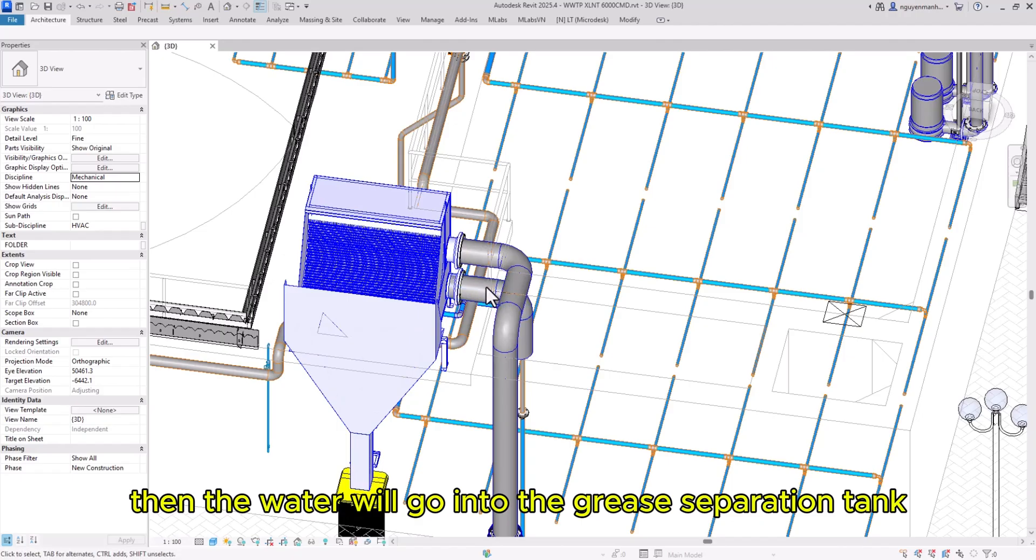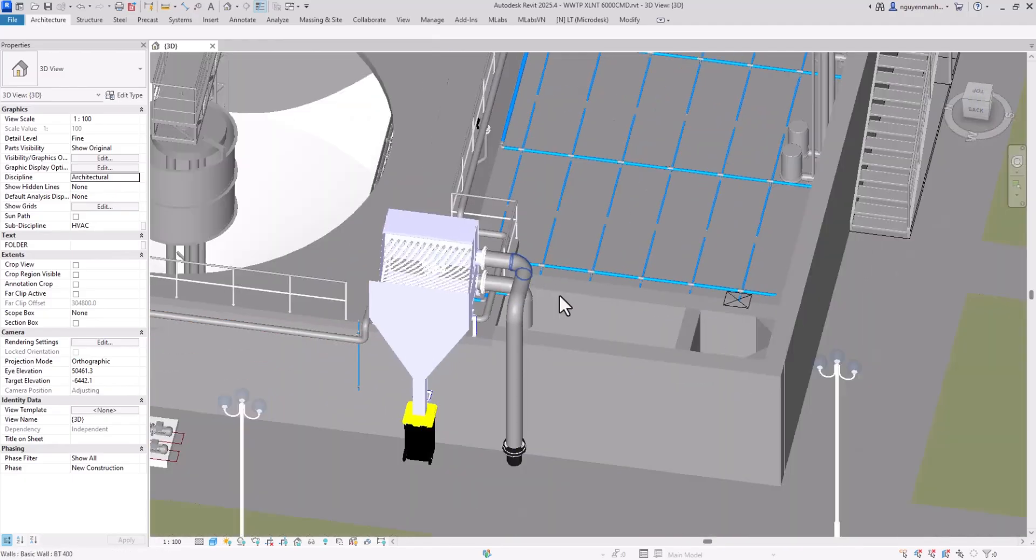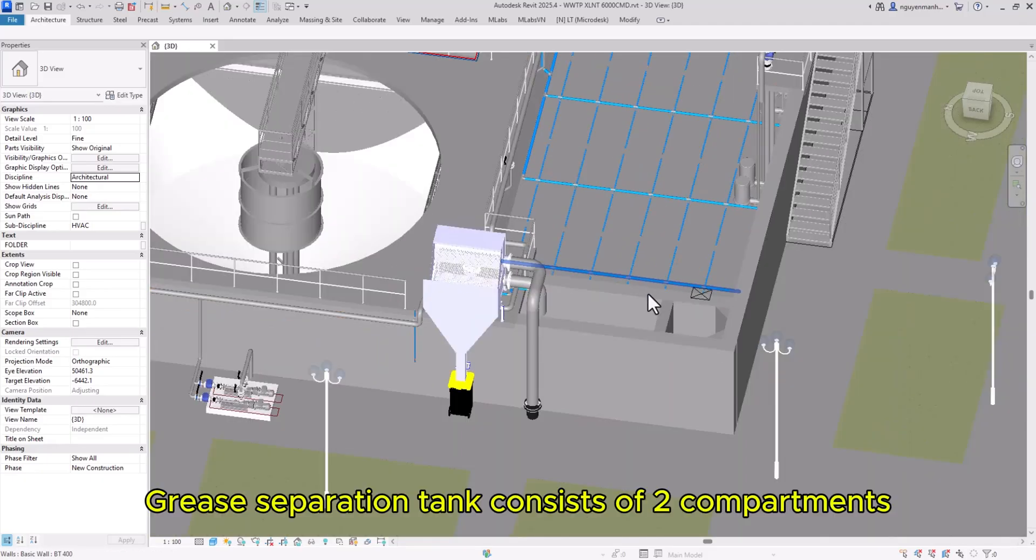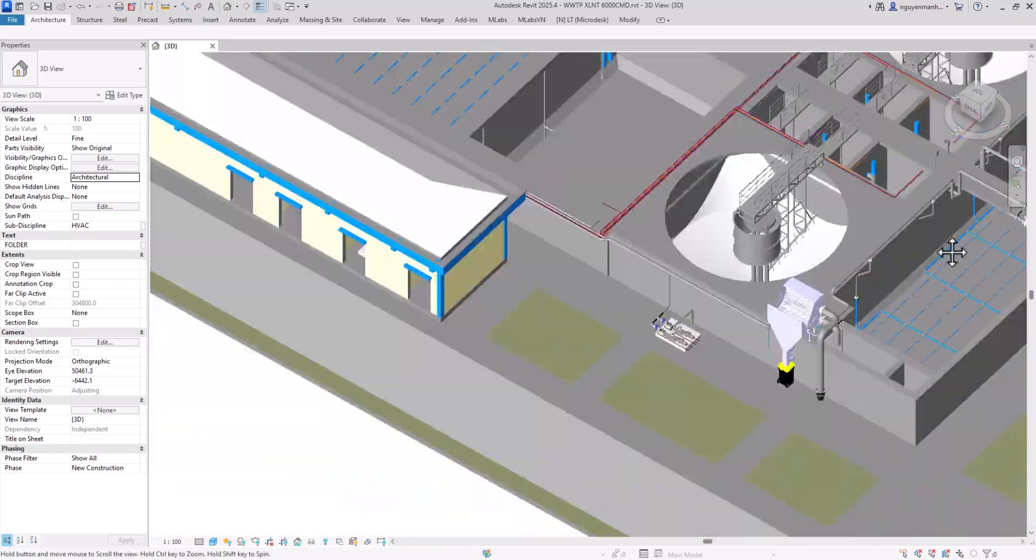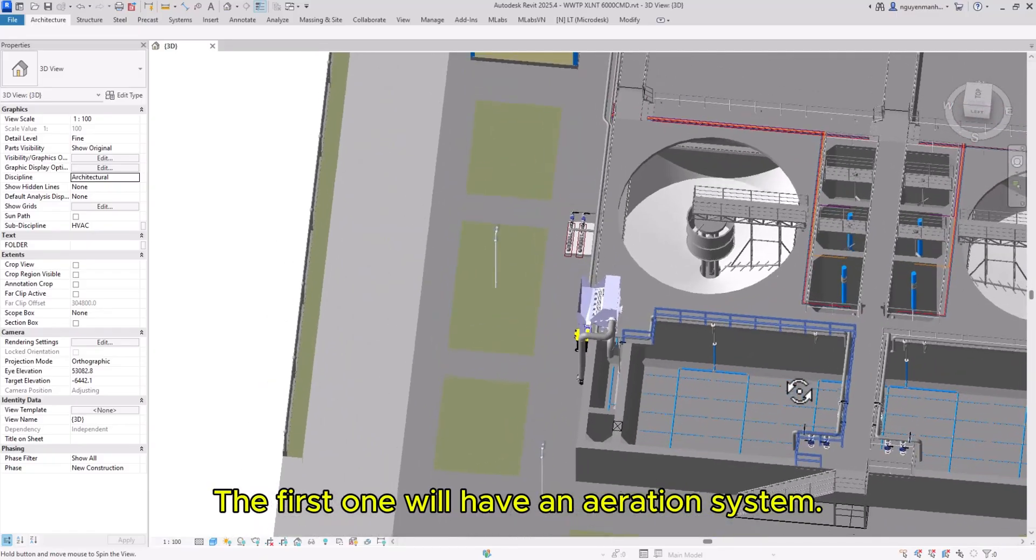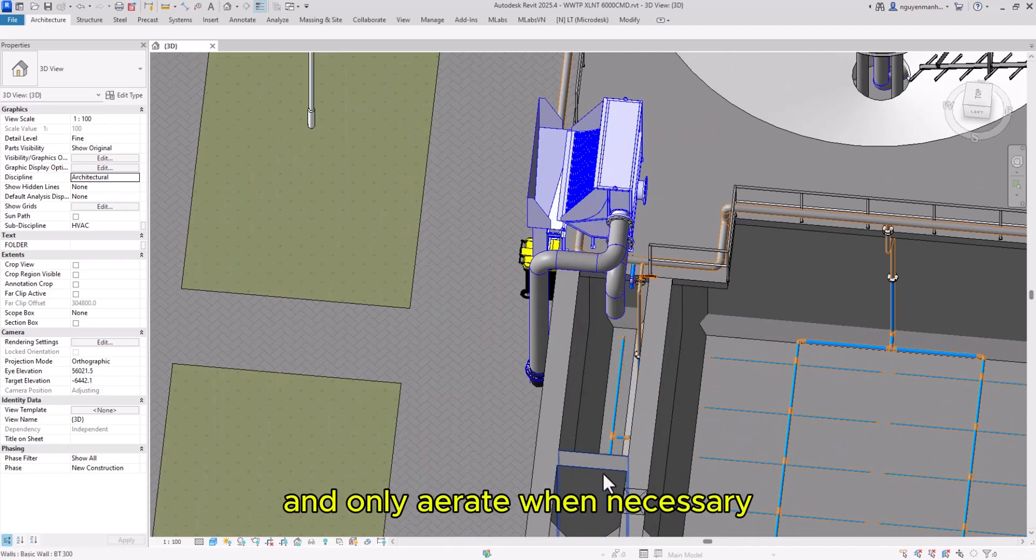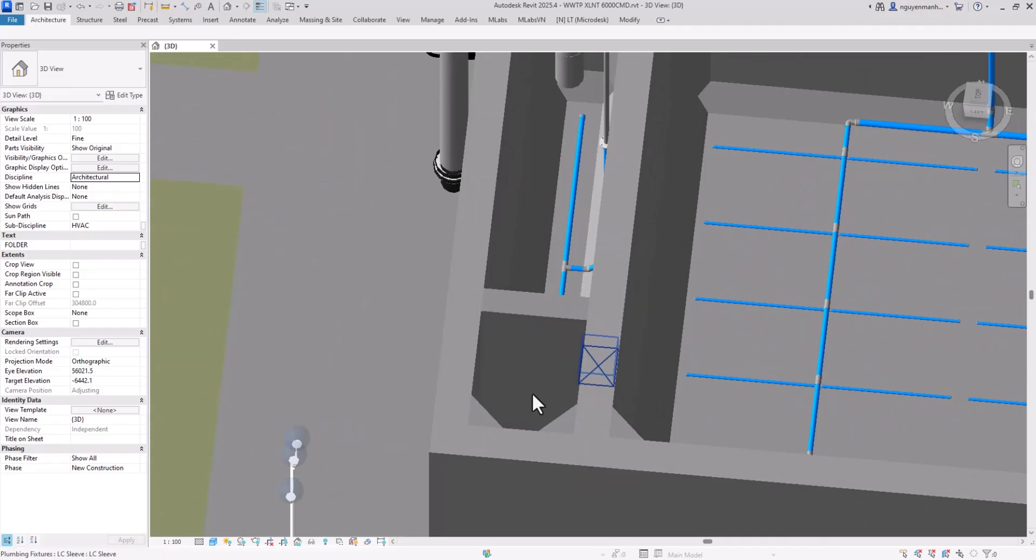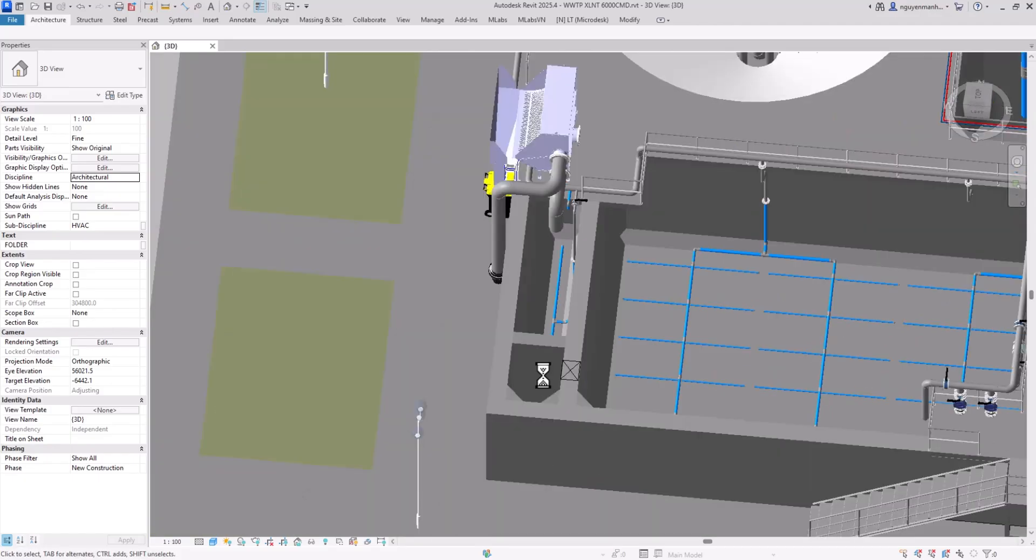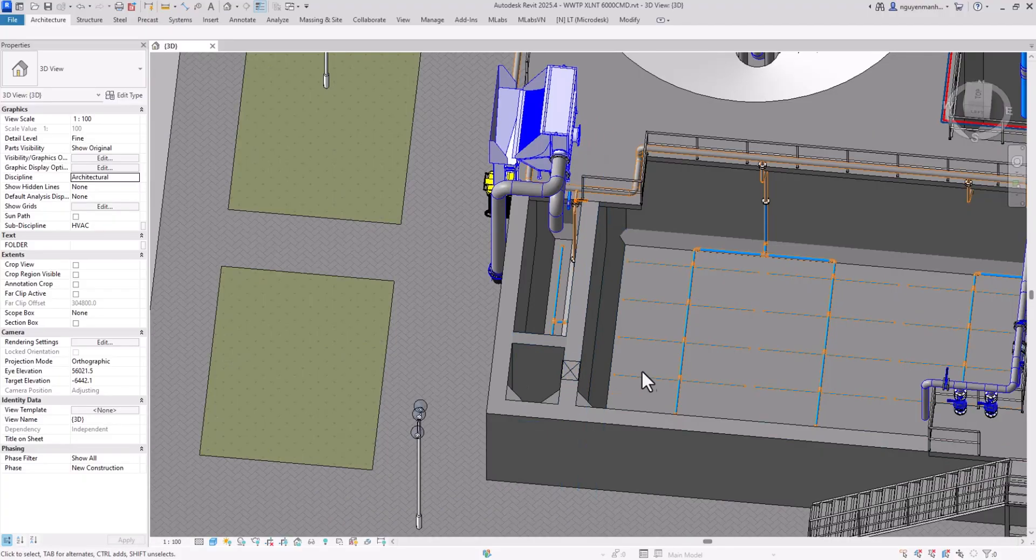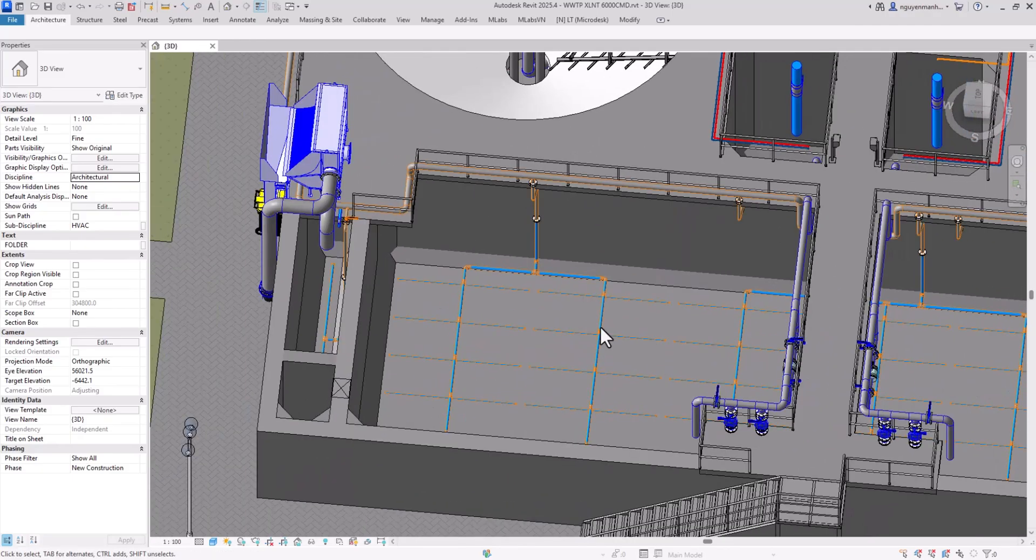Water then goes into the grease separation tank. The grease separation tank consists of two compartments. The first one has an aeration system and only aerates when necessary. The second compartment holds water. The water in the second compartment will overflow to the equalization tank.